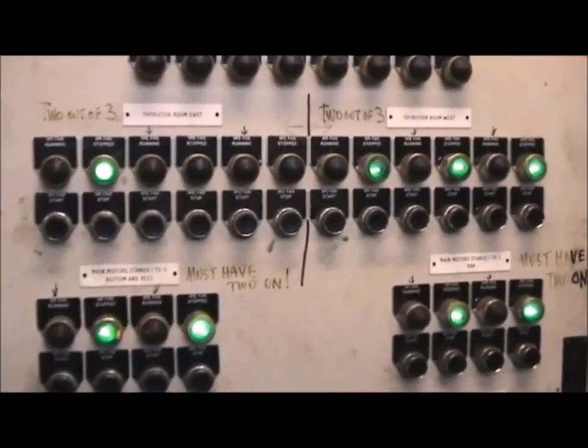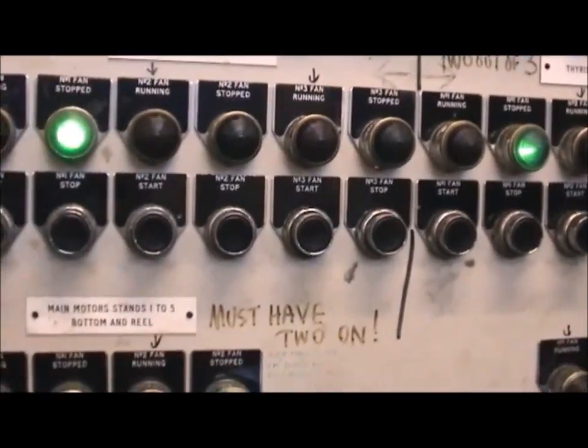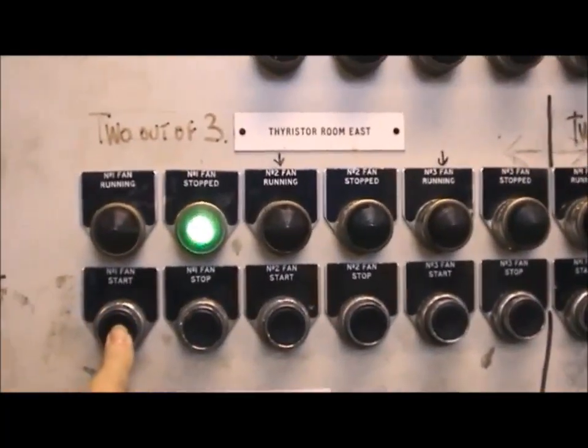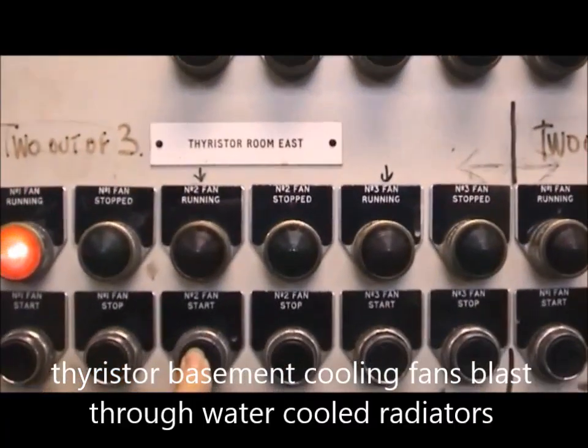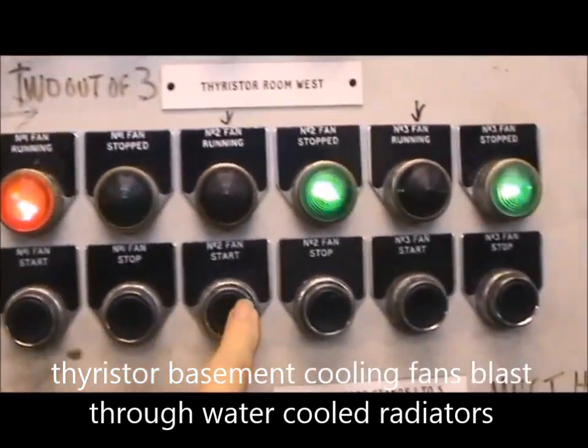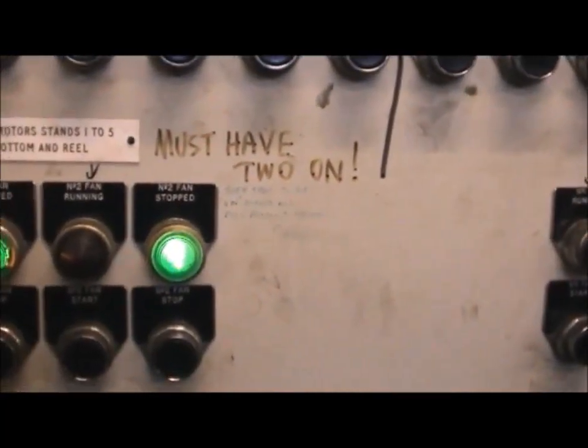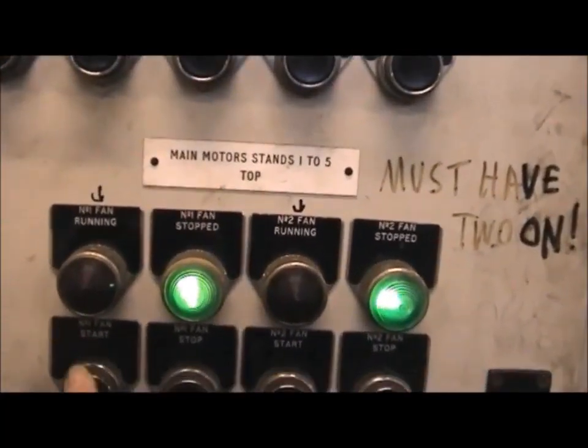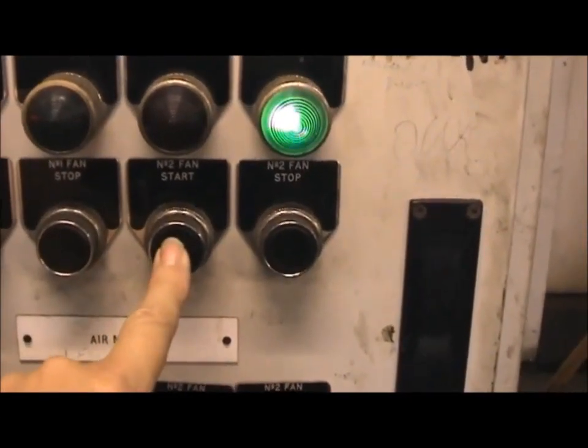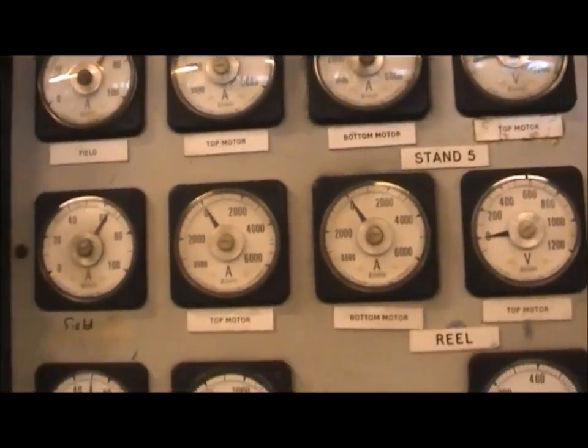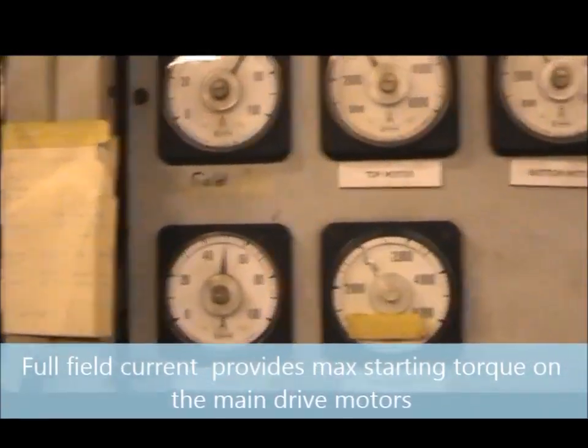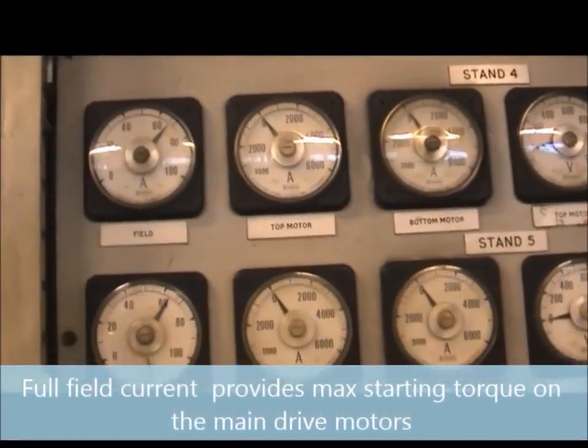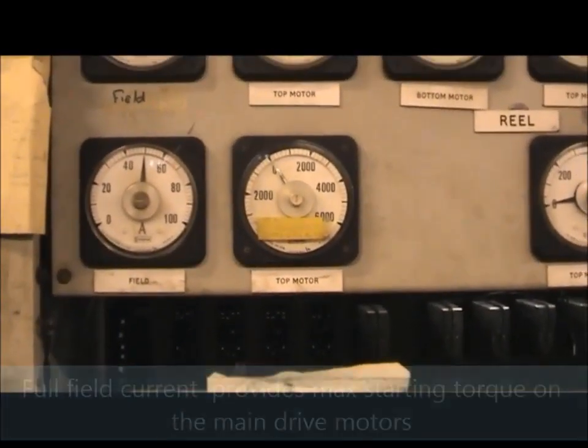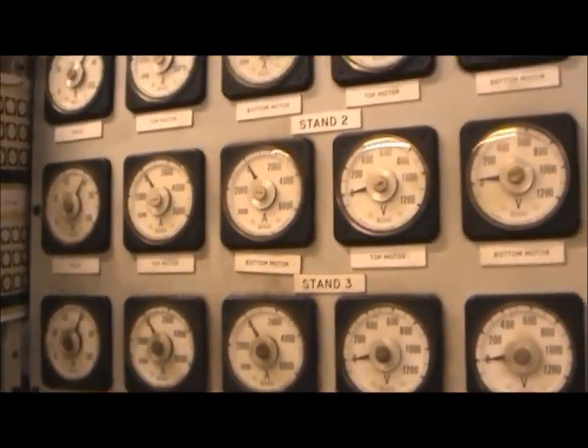I'll now start up the cooling fans. Two out of 3 in this section. Two here in this section. 2 in this section. Heard the contactor come in there, and the main drive motor fields now have gone up to their maximum value, full field values. Okay. Right. All fields healthy.